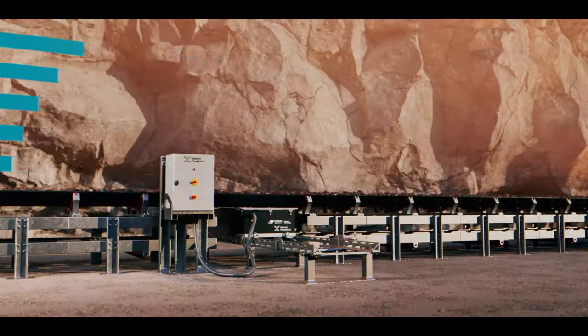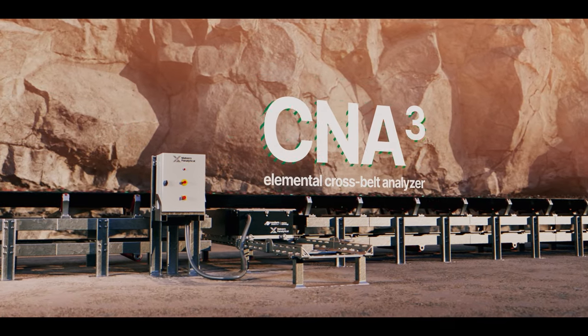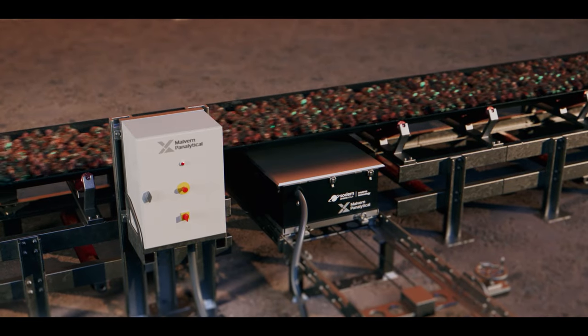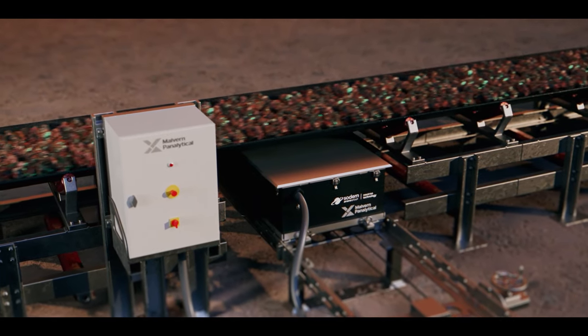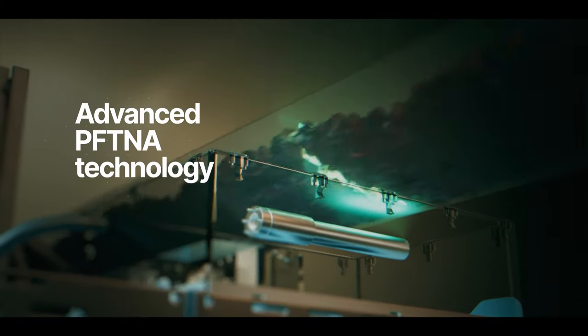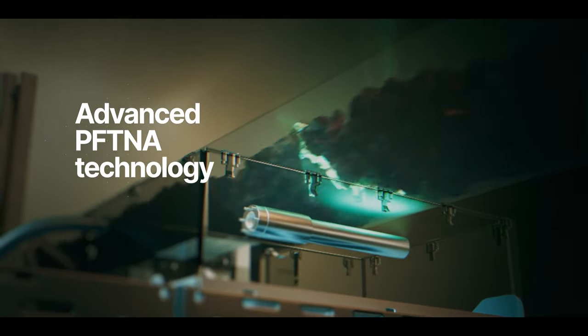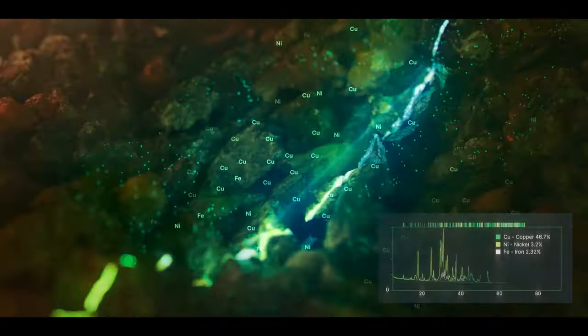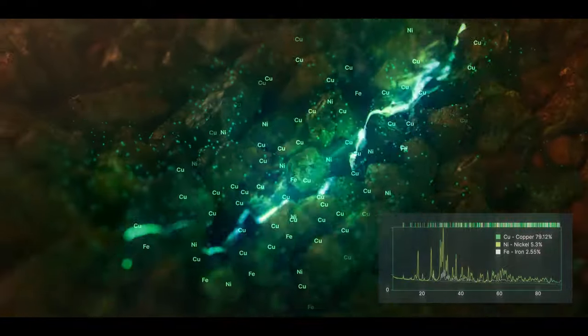With Malvern Panalytical's CNA, you can obtain real-time, highly accurate and reliable elemental analysis that helps you extract more metal from the ore. Based on advanced PFTNA technology, the CNA features Sodern Neutron technology in a new configuration that detects a range of elements directly on the conveyor belt.